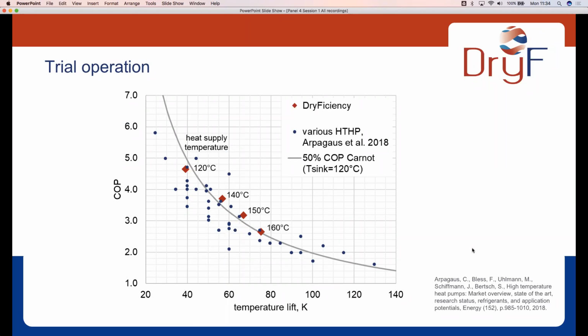On the x-axis we have the temperature lift, which is the temperature difference that is overcome by the heat pump. And on the y-axis is the COP. This is the ratio of the thermal energy that is provided by the heat pump and the electricity consumption of the heat pump. The red squares show the results of the trial operation. So we reached a COP of 4.7 for a heat supply temperature of 120 degrees C, and a COP of 2.7 at the highest temperature of 160.